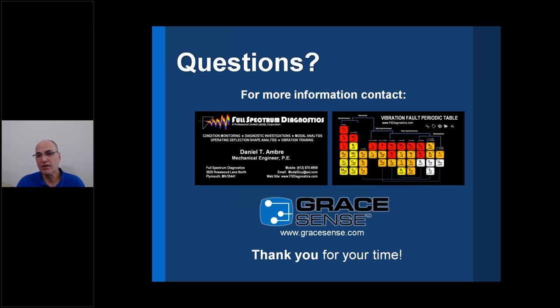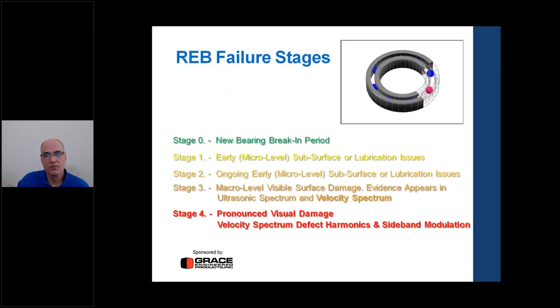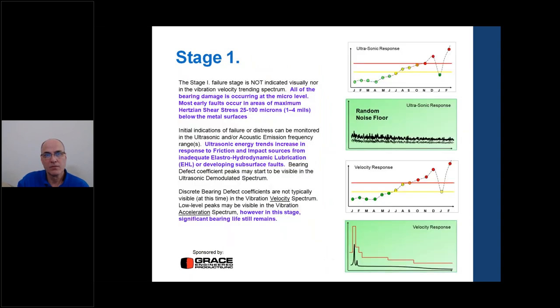First Q&A question: can frequency analysis notify maintenance that bearing lubrication is due, and how will freshly lubricated bearings compare to dry bearings in terms of frequency response? The distinction between a lubricated bearing and a dry bearing shows up in the ultrasonic spectrum as a change in noise floor level — like a carpet going up and down with loss of lubrication and extra friction energy. There should be no discrete bearing defect peaks; only the floor noise increases.